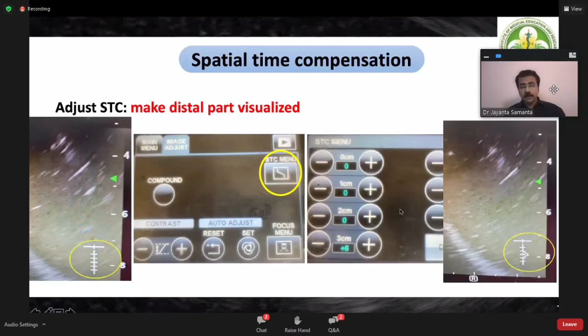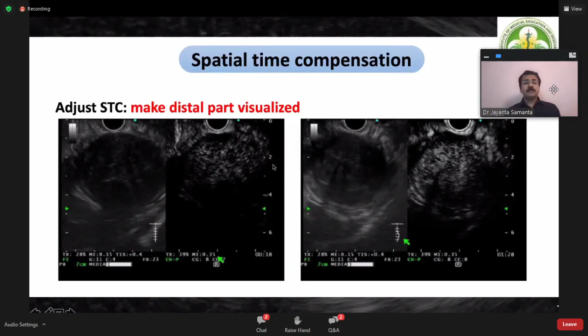So let's say this is a contrast enhanced EUS that is being carried out, and this is the default mode. You can see clearly that after the contrast has been injected, because this is a large lesion, we are not able to understand what the contrast enhancement pattern is at the distal part of this lesion. So what we do is we increase the STC at this level. Once the STC has been compensated, now you can clearly see the contrast enhancement pattern of the distal part. So this is the advantage of spatial time compensation, where we amplify the reflected waves that come from the deeper tissue in order to get a better image of the deeper tissues.